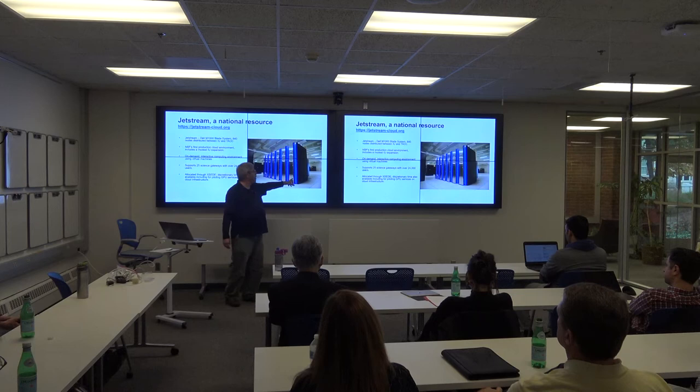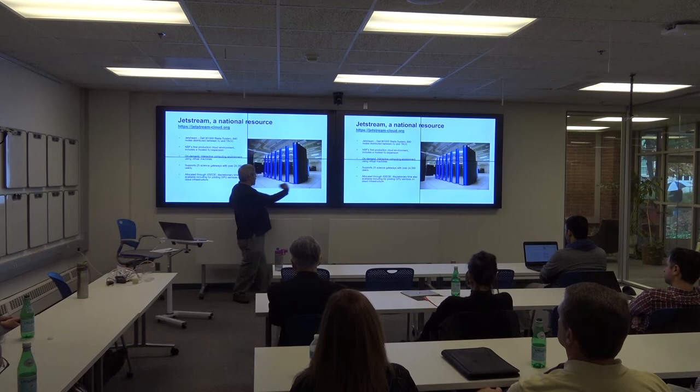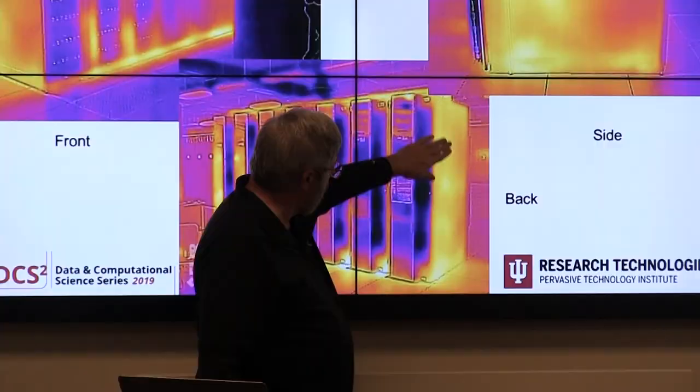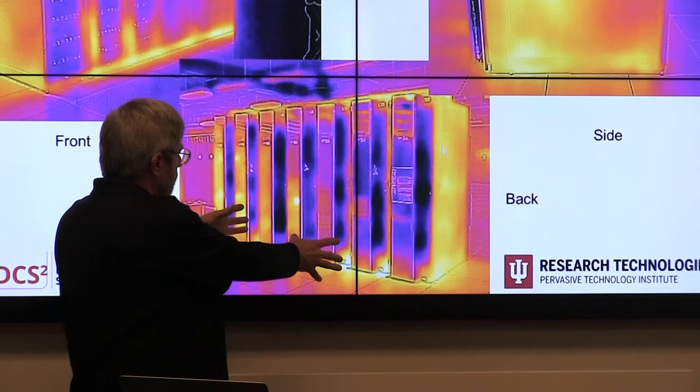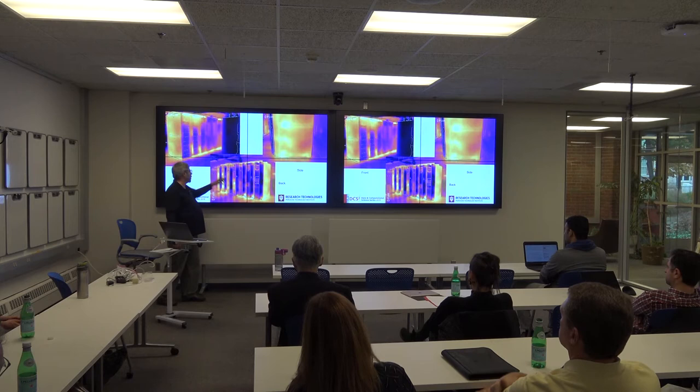You can see here in the front we have the cold aisle. Usually when you set up these computer rooms, you set up a cold aisle and then a hot aisle. So you'll have the back of two hot computers facing each other, and then the front will have two cold aisles sucking the cold air up. So these water chilled doors can actually take out more heat than we produce. But in these infrared pictures, you can sort of see that. This is cool and this is hot. So this would be the side of the machine. This is where that cooling radiator is. Right here in back of this system, there is nothing, but right over here, there's another computer blowing hot air onto the back of this system. So that's why it looks...